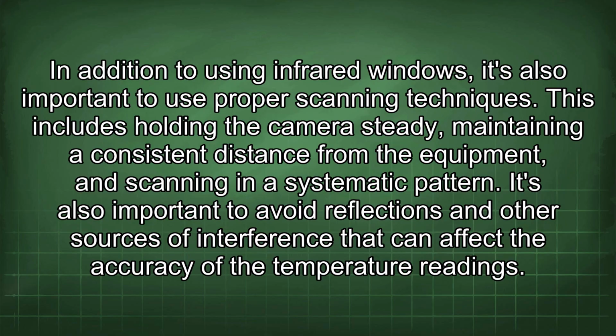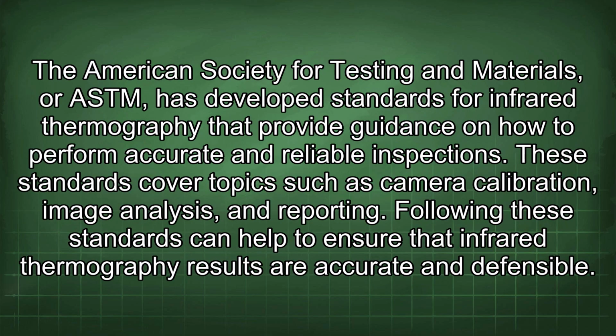In addition to using infrared windows, it's also important to use proper scanning techniques. This includes holding the camera steady, maintaining a consistent distance from the equipment, and scanning in a systematic pattern. It's also important to avoid reflections and other sources of interference that can affect the accuracy of the temperature readings. The American Society for Testing and Materials, or ASTM, has developed standards for infrared thermography that provide guidance on how to perform accurate and reliable inspections. These standards cover topics such as camera calibration, image analysis, and reporting. Following these standards can help to ensure that infrared thermography results are accurate and defensible.